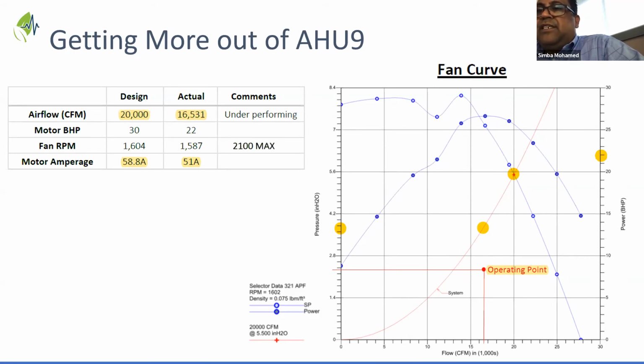So there's definitely something going on with this unit. Either we've got a major leakage, or there's something wrong with the blower and it's not performing as well as it should, and it's using a lot more power. So if we optimize this, we would be able to reduce the amp load and the energy, and be able to use this fan for multiple areas more than what we're using it for now.